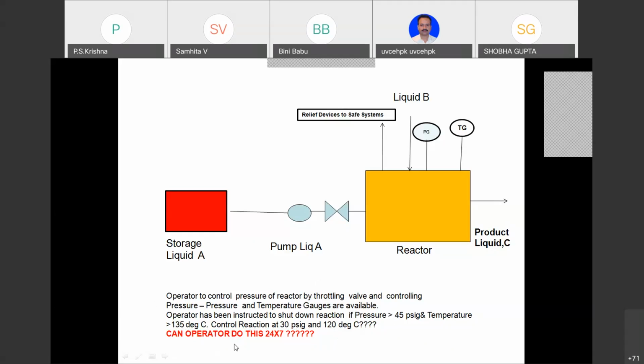Then the group decided to make a very stringent comment. They said, can an operator do this 24/7? A man is sitting there, however well he is trained. These two gauges are kept close to him on a probably simple panel, or it may even be a control room, and then this valve has to be manually operated. And if it slips for a second and puts more of the liquid going inside, then there could be a violent reaction and anything can happen. So this is unacceptable.